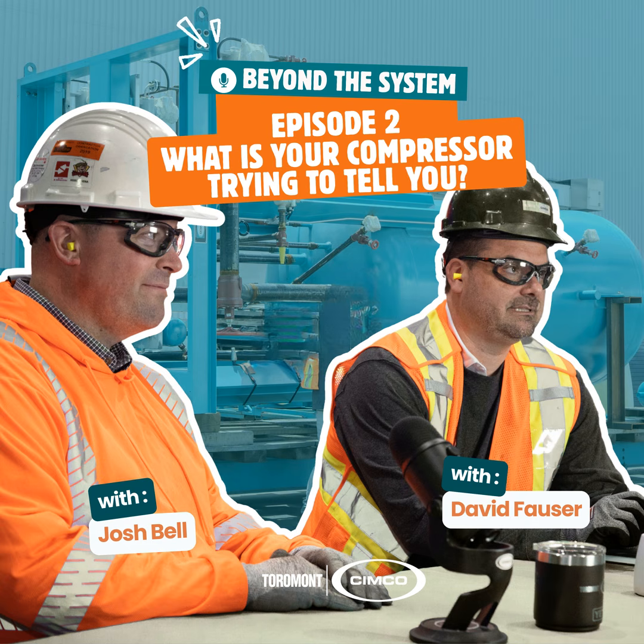Yeah, I mean, really, I can't say you're going to be listening for something very specific. I think what you're going to be listening for is something abnormal, something you don't typically hear. If you're the type of operator that shuts everything off every time you go in the room, you're kind of missing out on this. I would suggest always wearing hearing protection when the system's in operation, but you almost get a feel for the vibrations, the sound, for everything that's happening in the room.